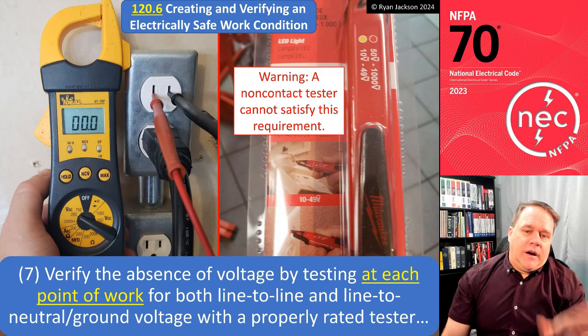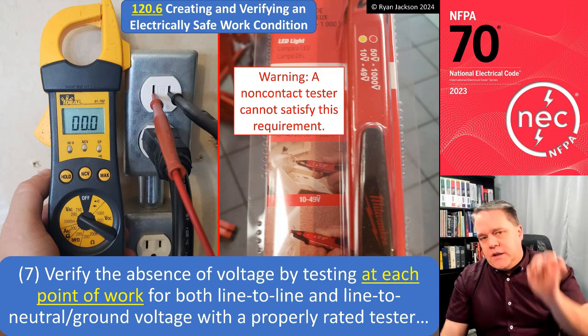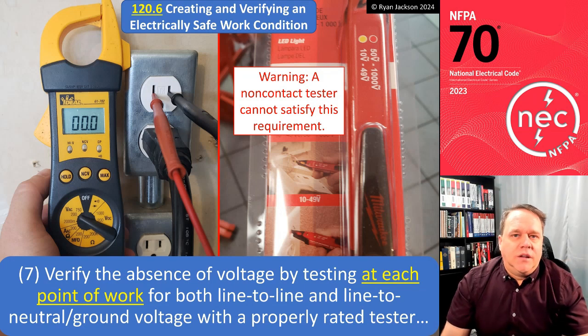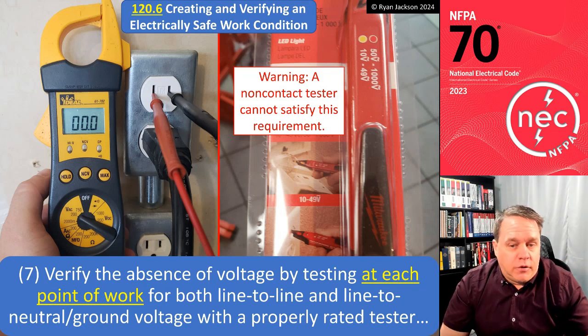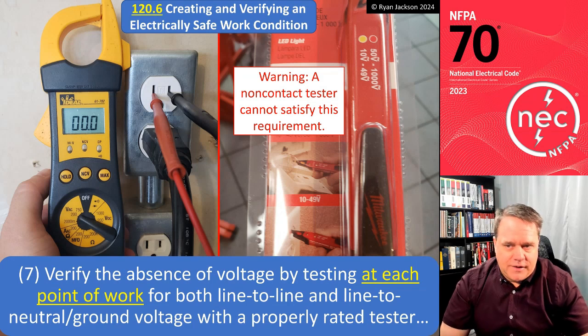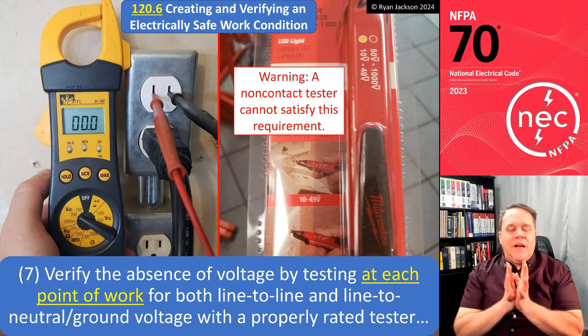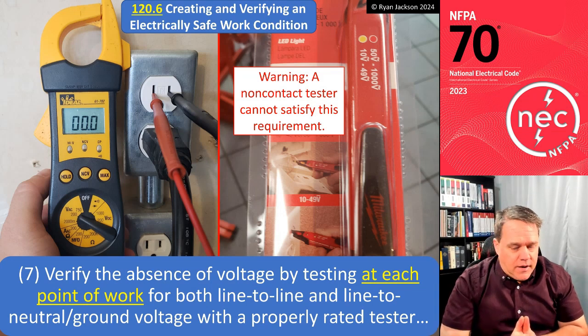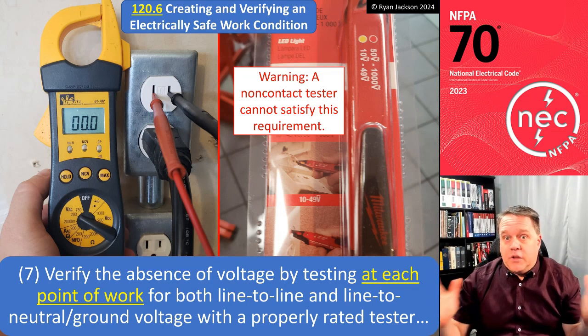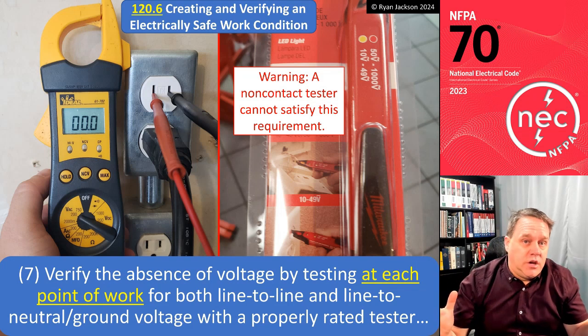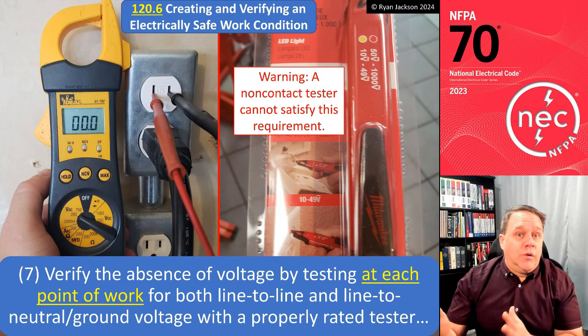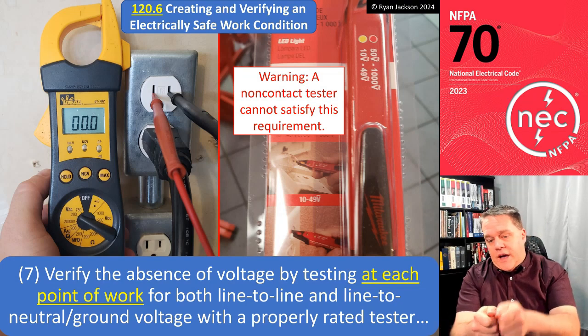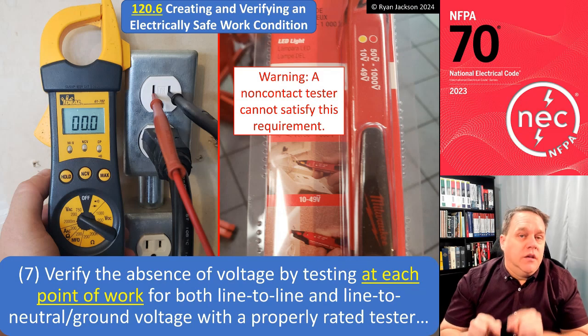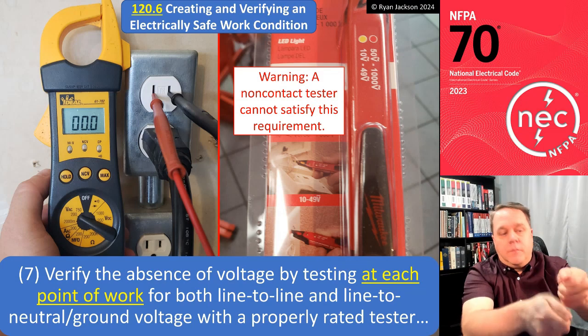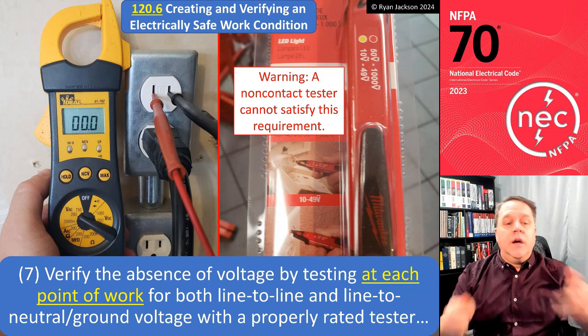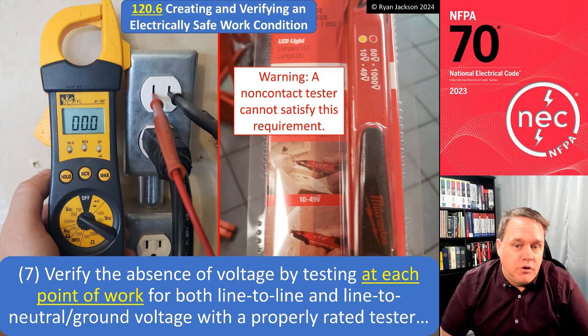Item 7, verify the absence of voltage by testing at each point of work for both line to line and line to neutral or ground voltage with a properly rated tester. So we need to make sure we're doing this at each point of work. If you have a large piece of equipment, this becomes even more critical. If you've got a large piece of switchgear, for example, multi-section switchgear, we need to make sure that every section that I'm actually working on is going to be de-energized. Don't just check one piece of the equipment that's massive. Make sure you're checking it where you're going to be doing the work.